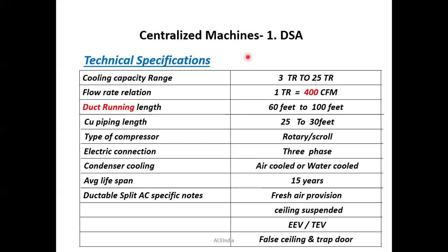Just one question: which type is better, air-cooled condenser type or water-cooled condenser type? What do you think? I feel water-cooled. Exactly, that's it. Water-cooled is much better than air-cooled, but typically air-cooled is much more affordable, isn't it? But in some areas, especially Middle Eastern countries, the ambient temperature is comparatively higher. I told you that day itself that R410A cannot be used with an air-cooled condenser when you have a high ambient temperature. In those scenarios, you can simply go for water-cooled condensers. So it's up to the refrigerant and up to the ambient itself.